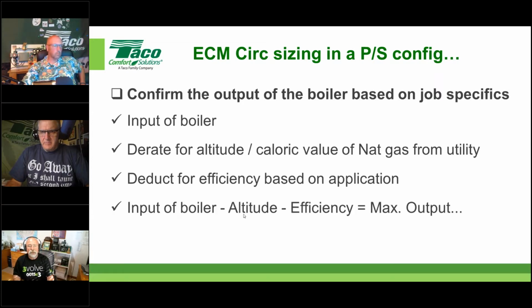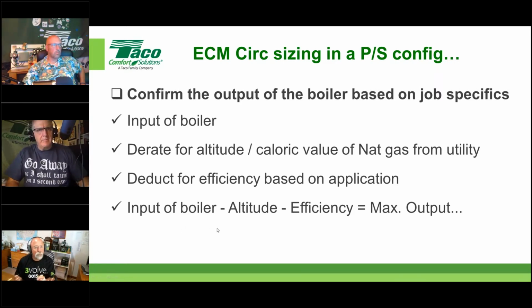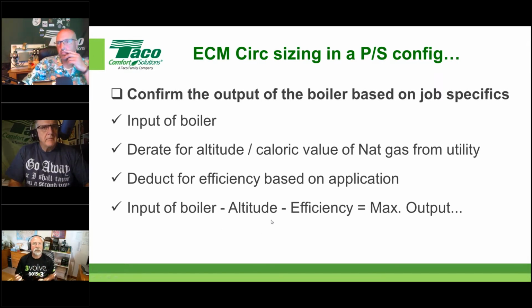Take the input, minus anything for caloric value based on altitude, minus the efficiency of that particular unit at the given application, and that'll tell you what the maximum output is. The other thing that's in consideration, folks, is: will you ever have that boiler go to high fire in a central heating call? That's a little sneak question there. I'm getting low on time, so we won't elaborate anymore, but I want to throw that out to you. How often will your ModCon boiler ever go to high fire in a central heating application?